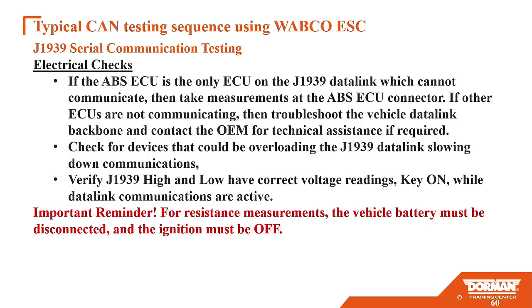Just a little side note: realistically, manufacturers design networks with some resistance to ground, you're never going to have a total, you're only talking about thousands. Just had to throw that in. And you can do the same thing for network to power: same as network to ground testing, except this time the ohm meter ground lead is moved to a power source. Anytime you do ohm meter testing, guys, keep it in mind, very important, make sure the power source is depowered.